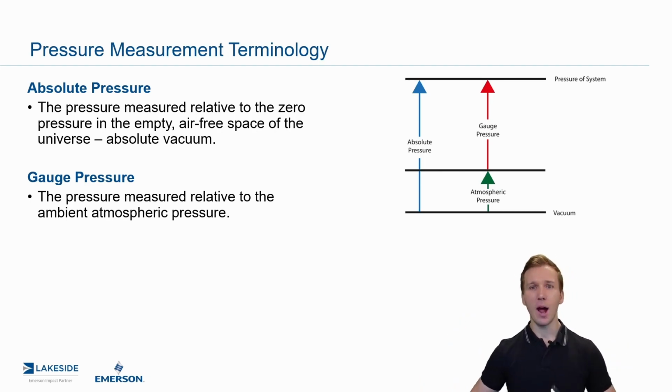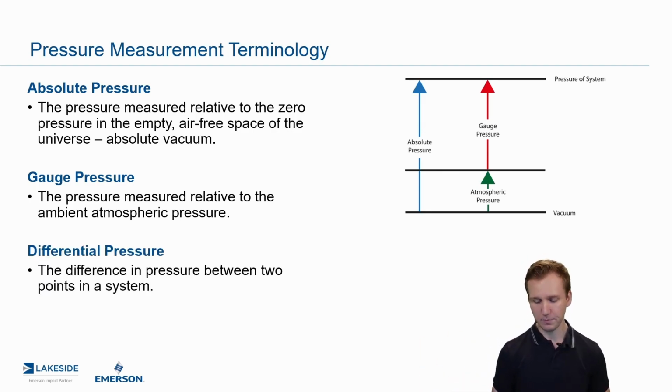So if everything around me here is being exerted on by the atmosphere at 14.7 psi, any measurement on top of that is going to be in addition to that 14.7. And depending on where we want to reference will impact our measurement. Now, some folks will measure in absolutes, generally if they don't want to have any uncertainties because atmospheric pressure is changing, that's fine. And most times, folks will use a gauge pressure measurement. And so if you have a 30 psig, then that means you have 30 pounds per square inch of gauge pressure, but in the absolute space, that would be 30 plus 14.7.